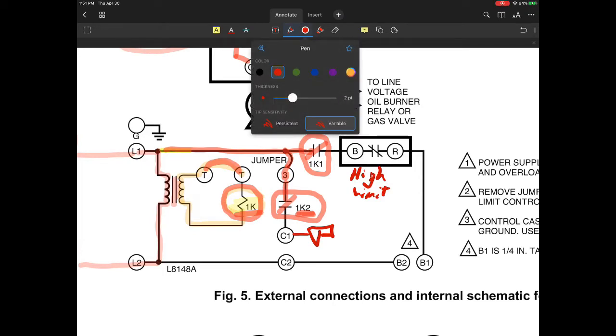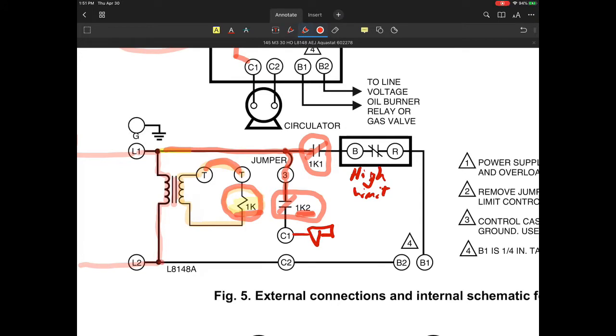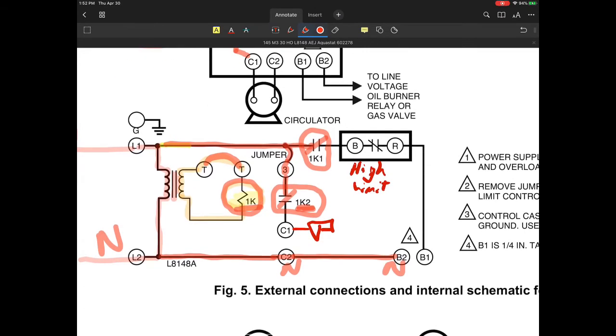This could be used to power some sort of circulating pump. And of course, C2 is actually going to be your neutral. So this is my neutral, that means this is my neutral, and that means this is my neutral. You'll notice B2 and C2 are different terminals, but they're tied together internally inside the Aquastat relay. So this would, of course, be my circulator neutral. That would allow you to energize a pump.